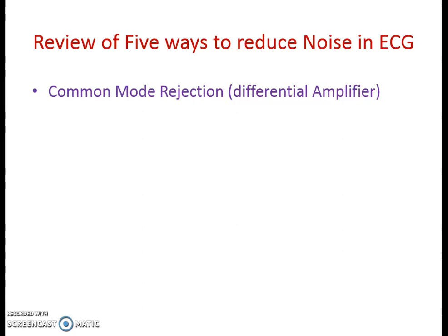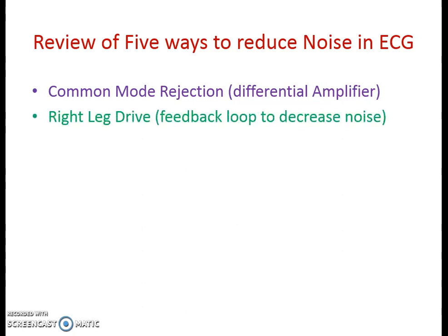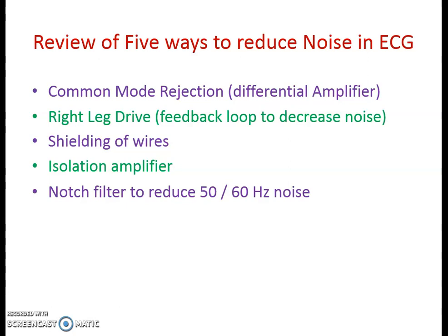Looking at the five strategies used to reduce noise in the ECG machine: first is common mode rejection — by using the differential amplifier and instrumentation amplifier we can reject the common mode signal. Second is the right leg driver, in which we send part of the signal back to the patient itself. Third is shielding of the wires. Fourth is using the isolation amplifier. And the fifth additional circuit used in the ECG machine is the notch filter, which also helps to reduce the 50 Hz or 60 Hz noise. By using these different strategies, we can reduce the noise in every ECG machine.